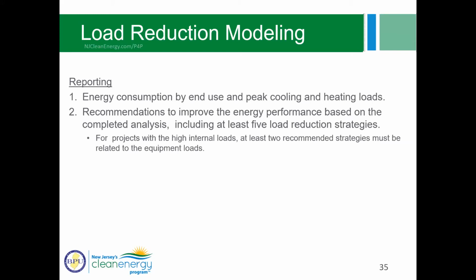In terms of reporting, you want to make sure that you report the energy consumption by end use and the peak heating and cooling loads for each of the alternatives that you analyzed. Then you want to include recommendations and at least 5 strategies for reducing load. If projects have high internal loads, you want to make sure that at least 2 of the recommended strategies are related to reducing those equipment loads. You don't want to neglect high impact end uses.